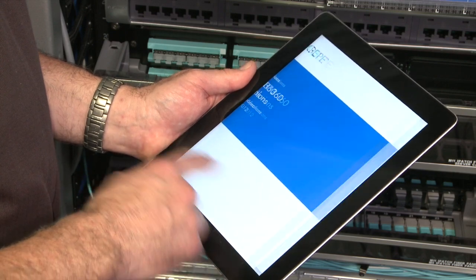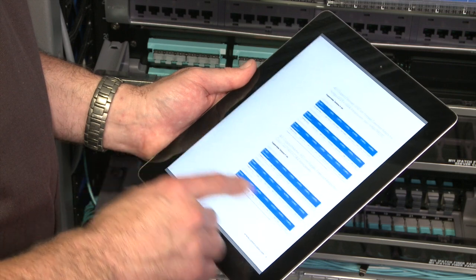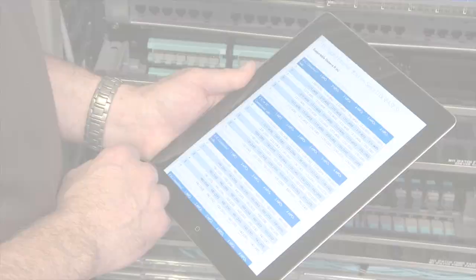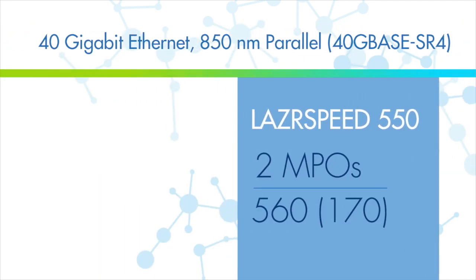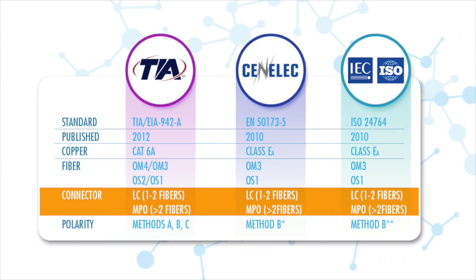Instapatch 360 sets design limits for the supported distance for a given application based on the number and type of intermediate connectors and the type of fiber being used. To upgrade to 40GBase SR4 over LazrSPEED 550 OM4 fiber based on two MPO connectors, the supported distance is 170 meters, which exceeds the distance defined by the standards. Unlike other solutions that require multiple types of trunk cords, Instapatch 360 trunks and modules are configured with the globally adopted method B polarity, which makes the upgrade process easy and straightforward.